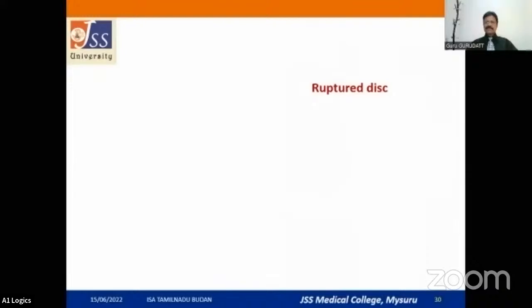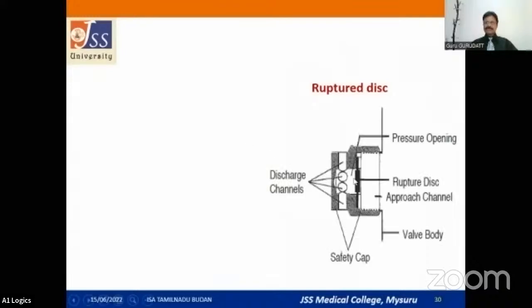The other thing I mentioned is the ruptured disc. The ruptured disc is usually made of copper. At a particular pressure, as the pressure starts increasing, the disc will rupture and vent out the gases.